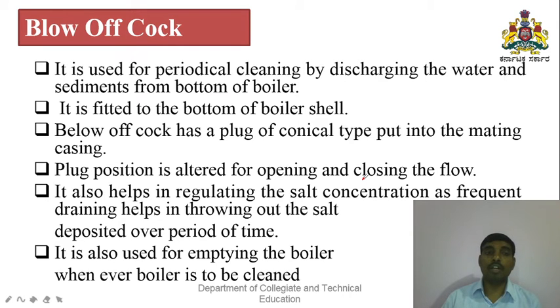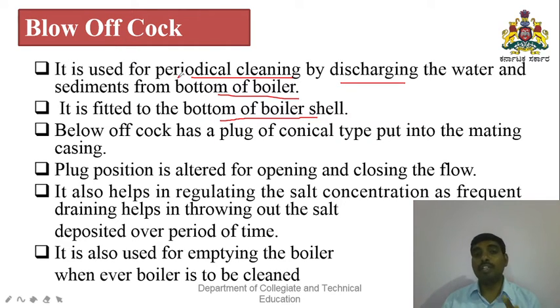Next, blow-off cock. It's a device used for periodical cleaning by discharging water and sediments from the bottom of the boiler. It is fitted to the bottom of the boiler shell. The boiler shell containing water may have some sediments or foreign particles, which should be removed periodically. For that purpose the blow-off cock is used.